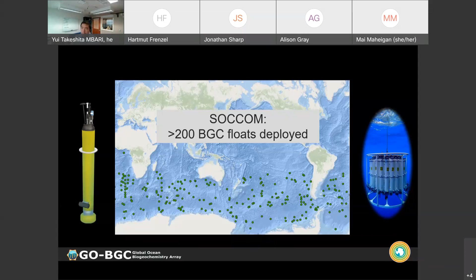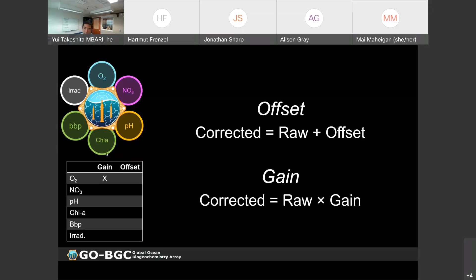We will start going through the adjustments that we apply for all of these parameters. They are basically either an offset, which is just a constant value, or a gain, which is a multiplicative correction. Offset is just the raw data plus a constant, and for a gain, you multiply the raw data by the gain. Some sensors will require only a gain or an offset, and some sensors will require both. I will go through all of them and keep updating this table on the left as we talk through each parameter.